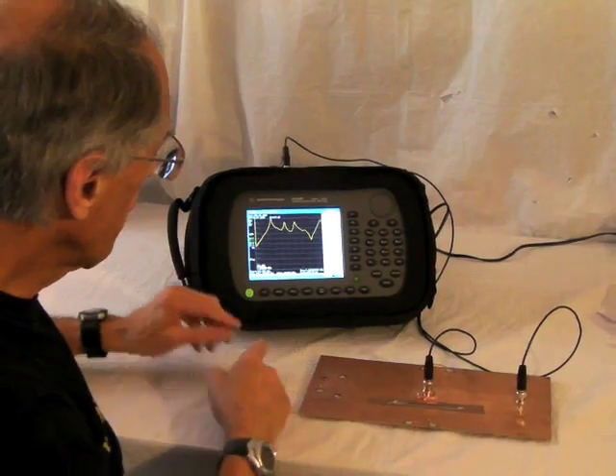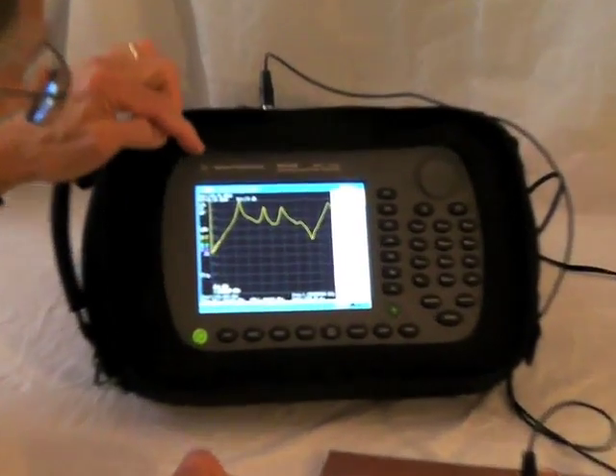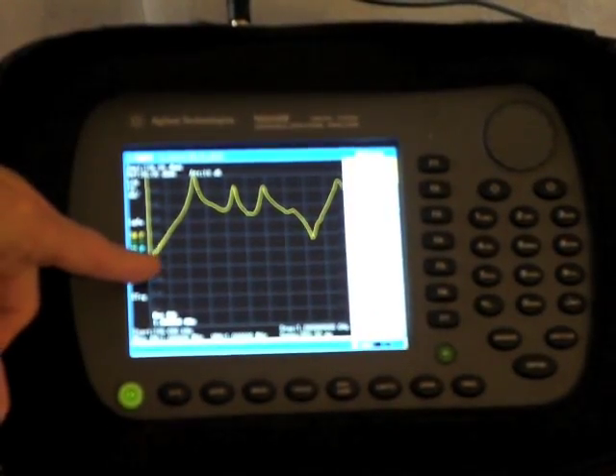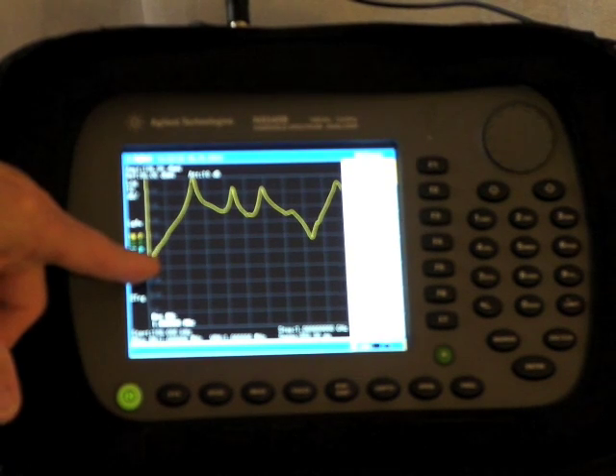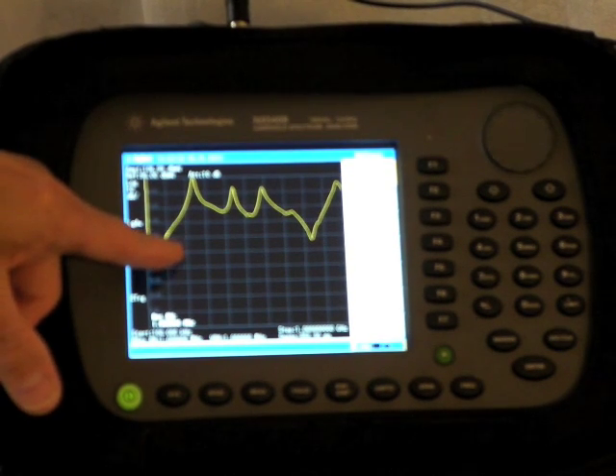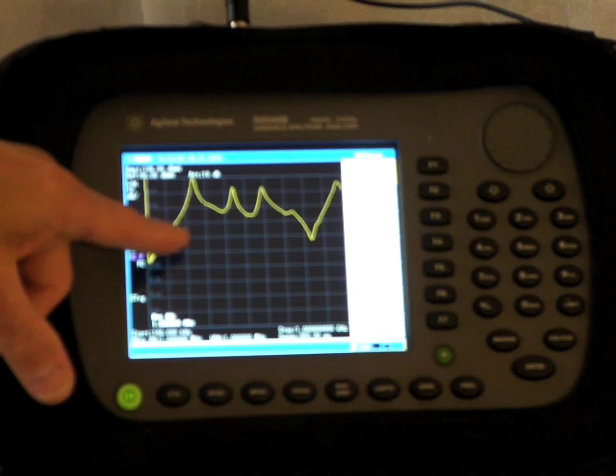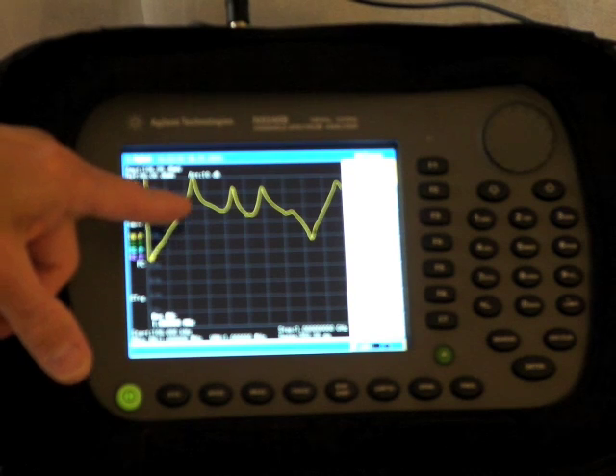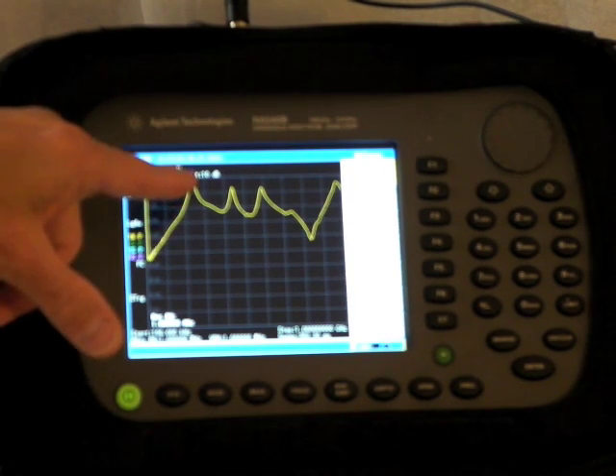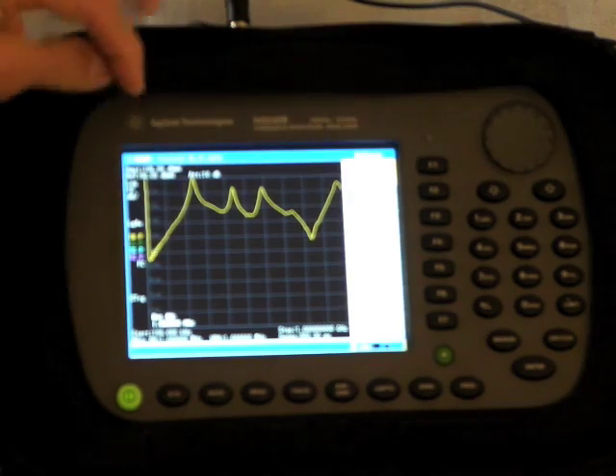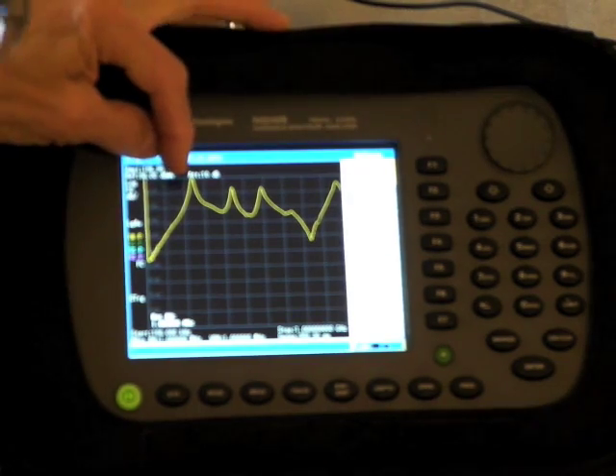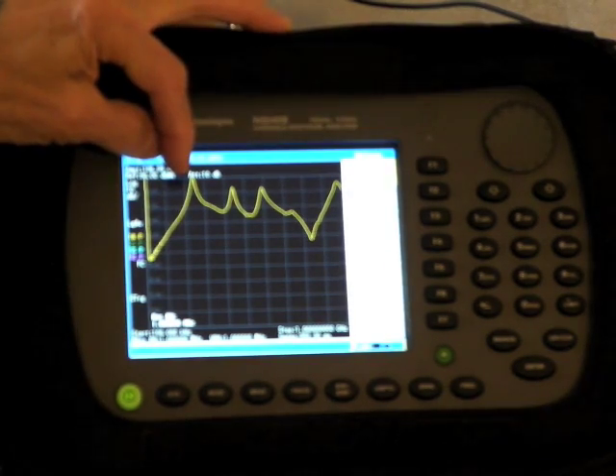Other than that, the same. But now, as we zoom in on the spectrum analyzer again, look what happened. We went from about 35 dB microvolts here, and there was a little peak to about 45 or so. 10, 20, 30, 40 — and it's slightly off the scale here, so it's more than 40 dB higher, and that frequency is about 240 megahertz.